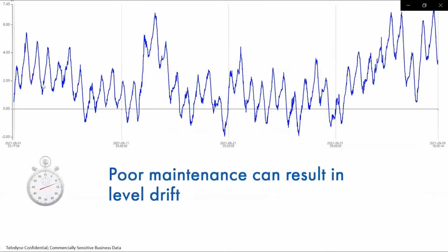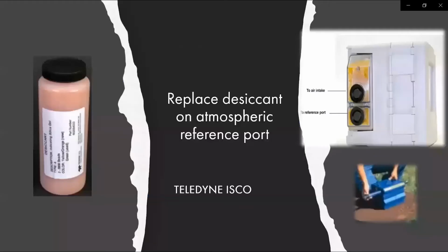Now this graph here, what we're looking at is level, and you can see it's actually going below zero several times. This is an example of where your sensor no longer has reference to atmospheric pressure. And so as the barometric pressure changes, all of a sudden now all my levels are going higher and lower. And that's usually seen by levels that are going to go one direction, or it actually goes above and below zero instead of remaining consistent.